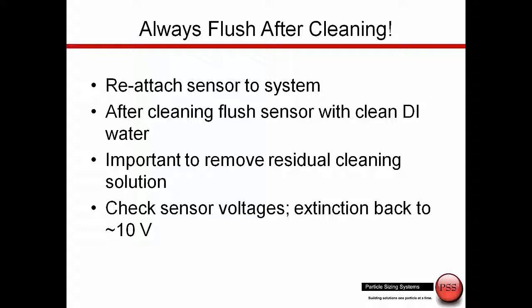After flushing the system, check the sensor voltages again. The extinction value should be back up near 10 volts. Remember you can always see the original voltage levels on the service code on the side of the sensor.